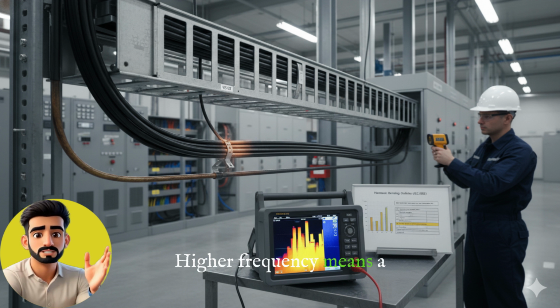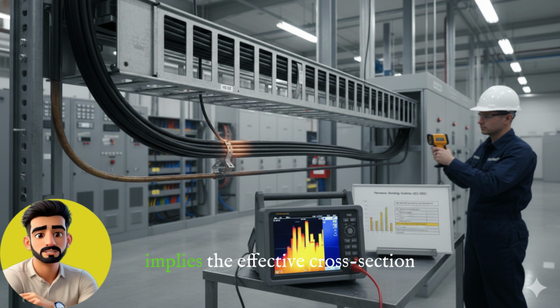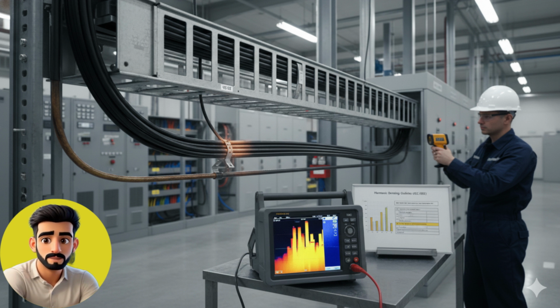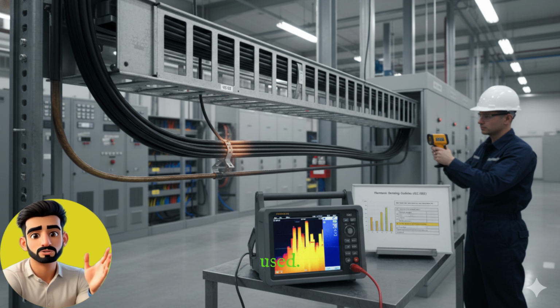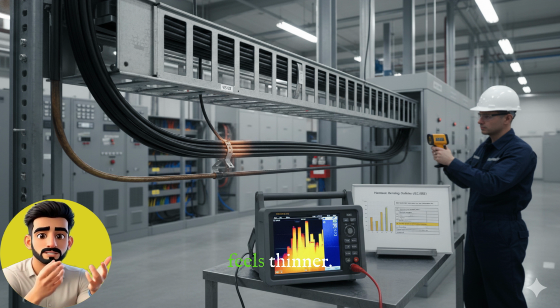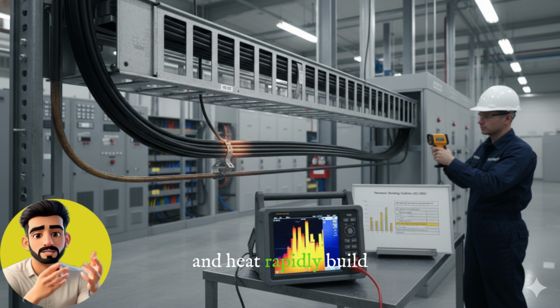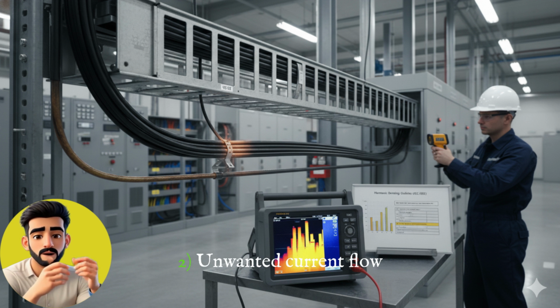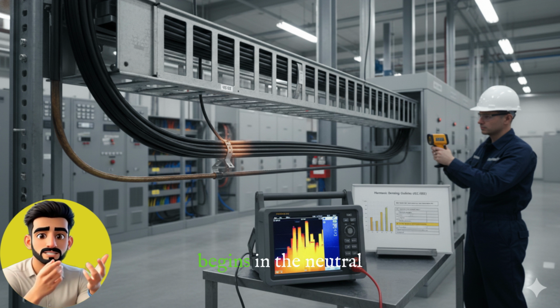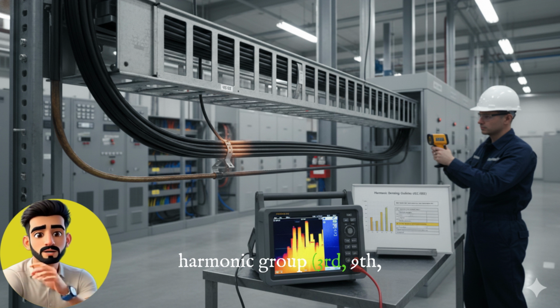Higher frequency means a deeper skin effect, which implies the effective cross-section decreases. In simple words, the copper inside the cable is available, but harmonics prevent it from being used. That's why the cable feels thinner, and heat rapidly builds up. 2. Unwanted current flow begins in the neutral, especially in the 3rd harmonic group: 3rd, 9th, 15th, and so on.